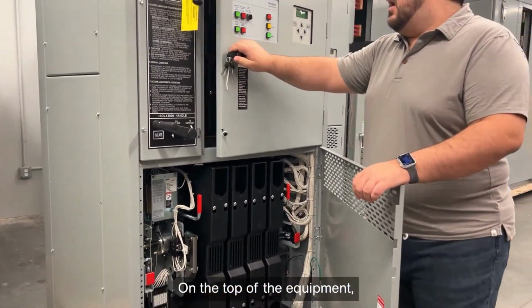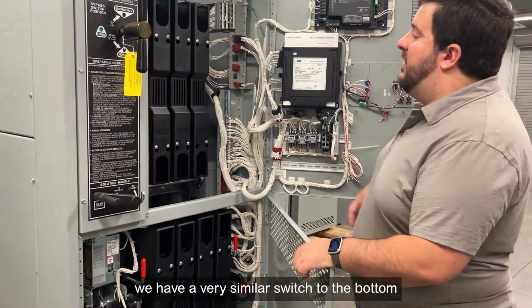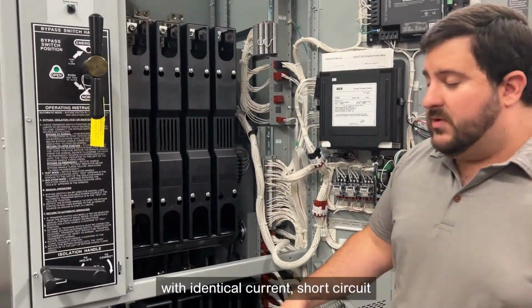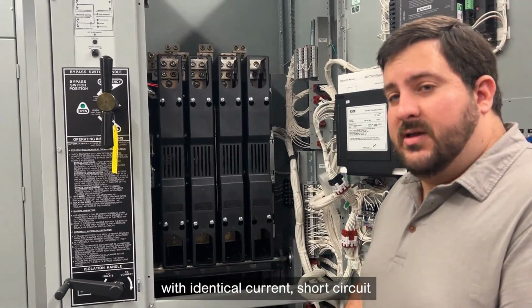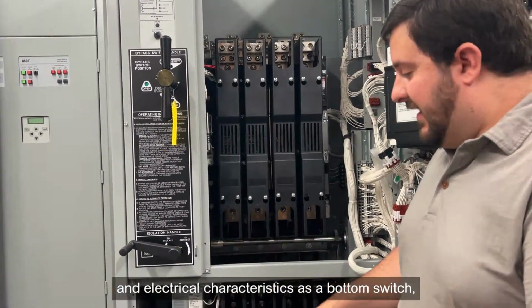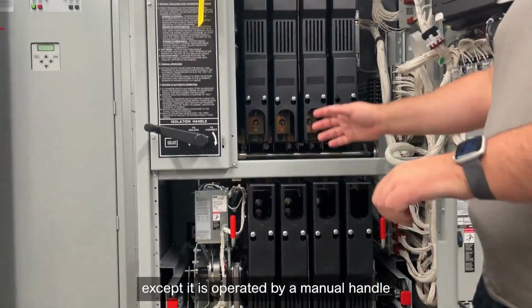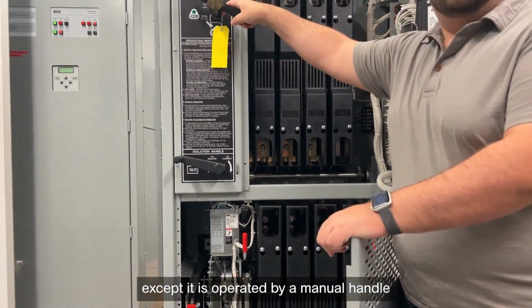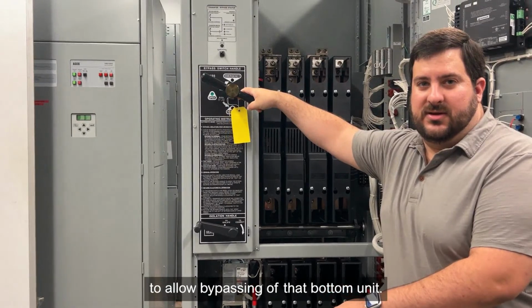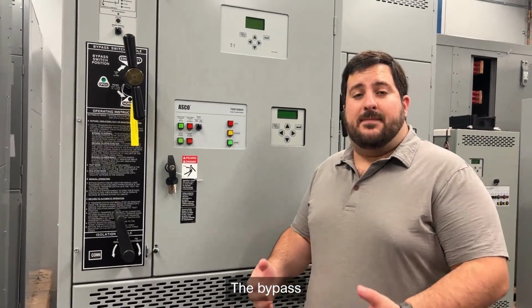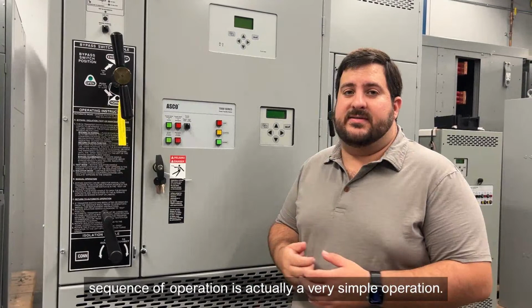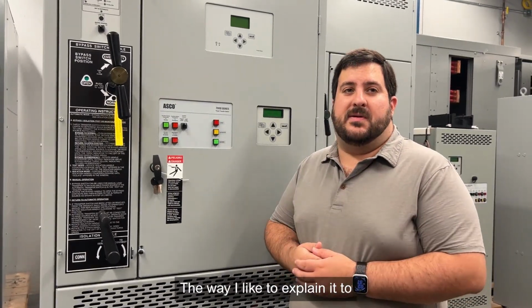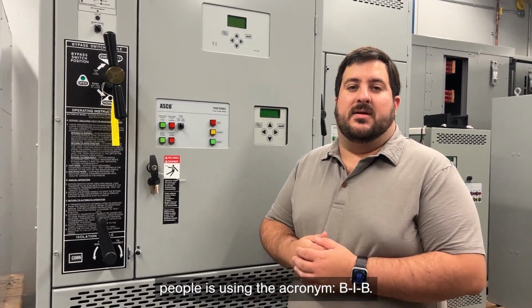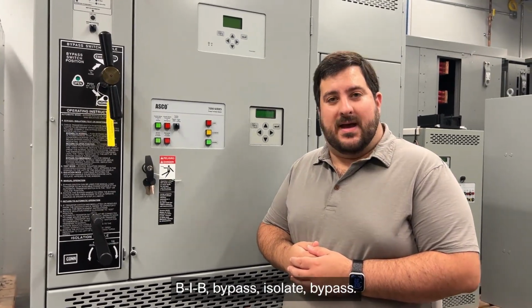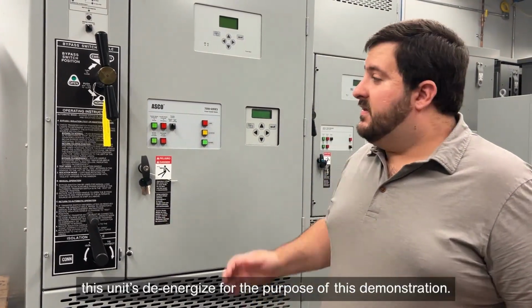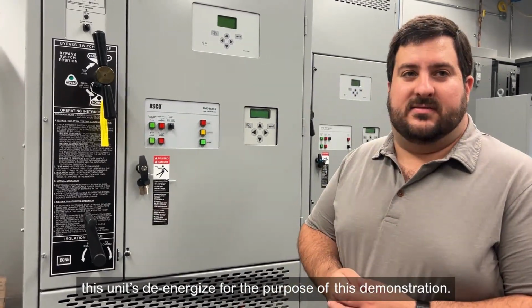On the top of the equipment, as you can see, we have a very similar switch to the bottom with identical current, short circuit, and electrical characteristics as the bottom switch, except it is operated by a manual handle to allow bypassing of that bottom unit. The bypass sequence of operation is actually a very simple operation. The way I like to explain it to people is using the acronym BIB, B-I-B. Bypass, isolate, bypass.